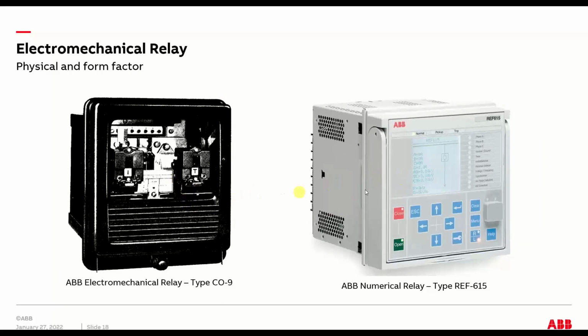Here's just a comparison in form factor. These two relays are about the same dimensions. This might be a little bit bigger, but you can see there was a lot of intentional design to make it mimic this relay, because one of the interesting features is that the internals of this relay are drawn out. You can open this box and pull out this relay so it can be tested. Same thing here. This is a handle that pops out. So the back part stays within the gear, but you can draw this relay out, test it on a bench, or even just swap it out if you had a problem with it.